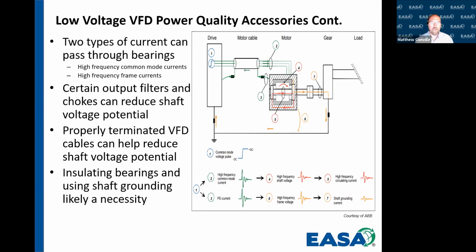There are two types of current that can pass through bearings. There's common mode currents, which are created by common mode voltages, and that's done by the variable frequency drive and switching. And the other one is going to be frame currents, or what we call PE current. The one that we've got to be really worried about is, we might have shaft grounding to help mitigate the ground current, but now we might have some of this high frequency common mode current too. So we might have to go to isolating both bearings instead of just one, or whatever the case may be. But it exists. So if we use a properly terminated VFD cable, that outer shield, if it's terminated right, will actually take that high frequency current straight to the frame, and it no longer becomes an issue.